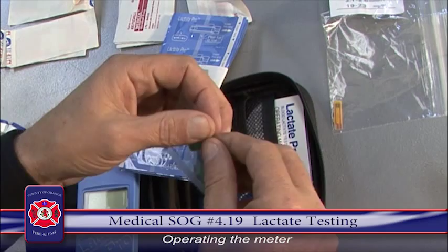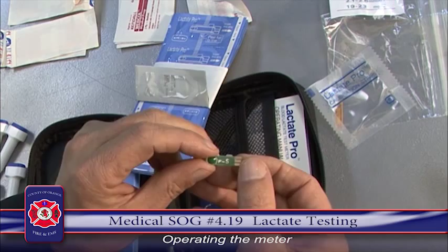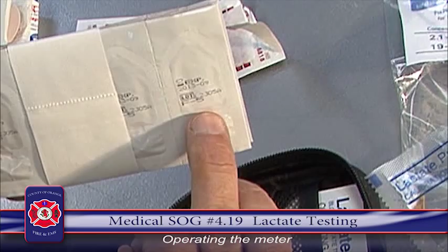And that's very simple. What's important, though, is that when you're finished with this, you put it back in this container. If the electrodes on this little testing strip get contaminated, it's going to affect the test that you get. You'll have an erroneous test. Now, the other thing when you're talking about testing versus calibration, as I said earlier on, they're two very distinct things. These are the test strips. They don't come in the bottle that you normally see glucose testing strips come in. This is what you'll see them in.